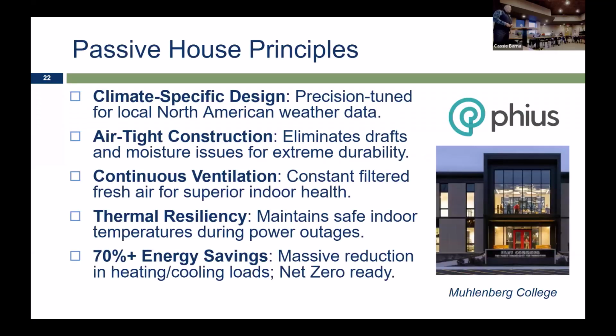There's nothing wrong with passive house principles. As a matter of fact, everything is right with them. It's common sense, and this structure is beginning to get a lot of traction. When I went back to that property we were talking about planning in the township, passive house principles were first and foremost: orient the building correctly, create a tight envelope, have efficient systems, use air exchange we can control rather than infiltration we can't control, build a controlled environment. When we do that, we get to an EUI typically about 20.